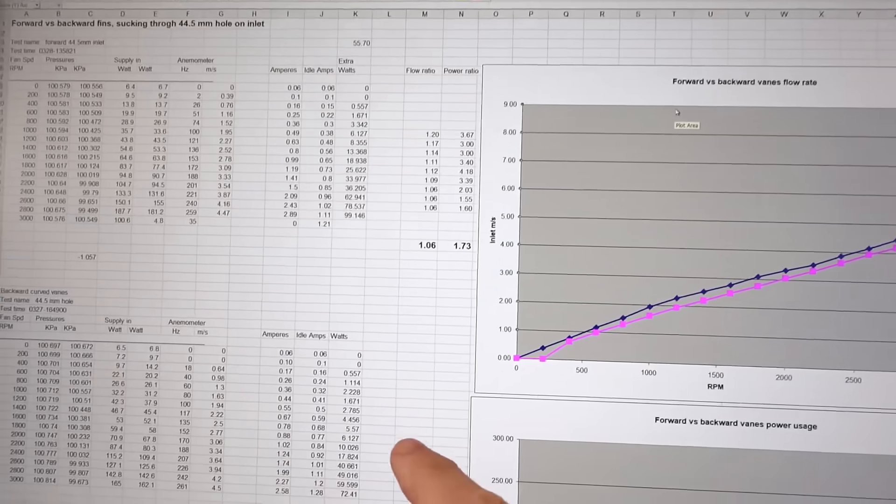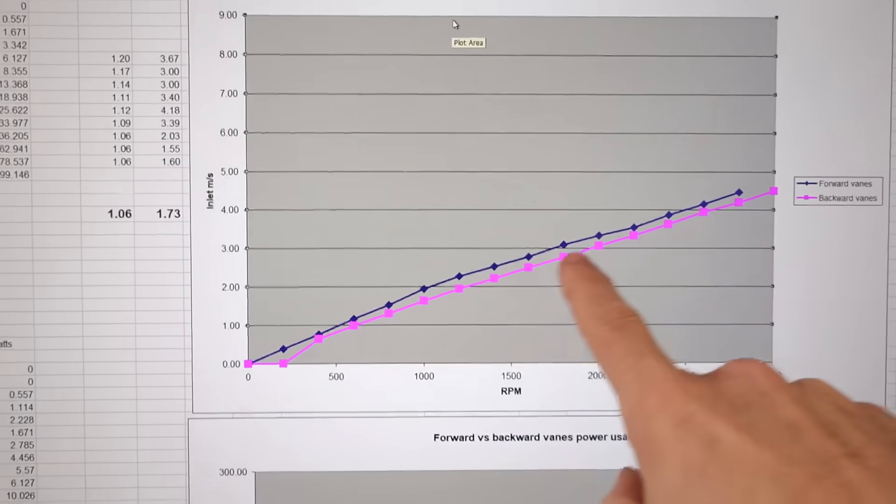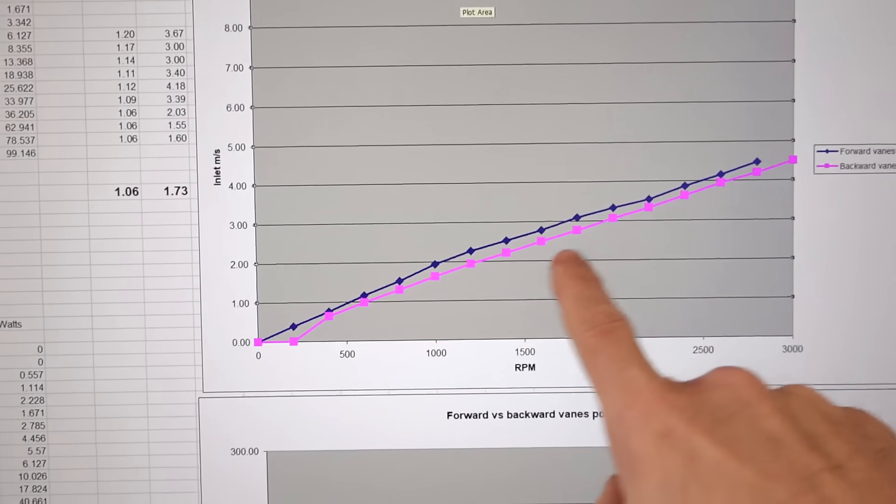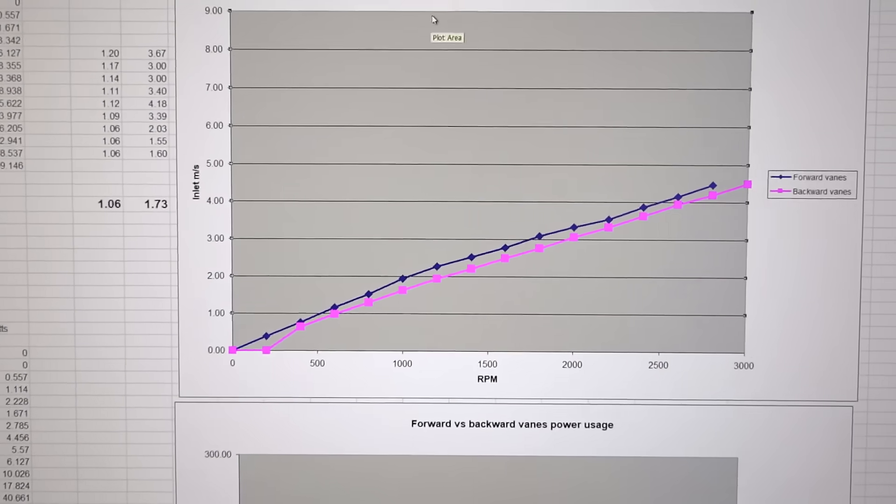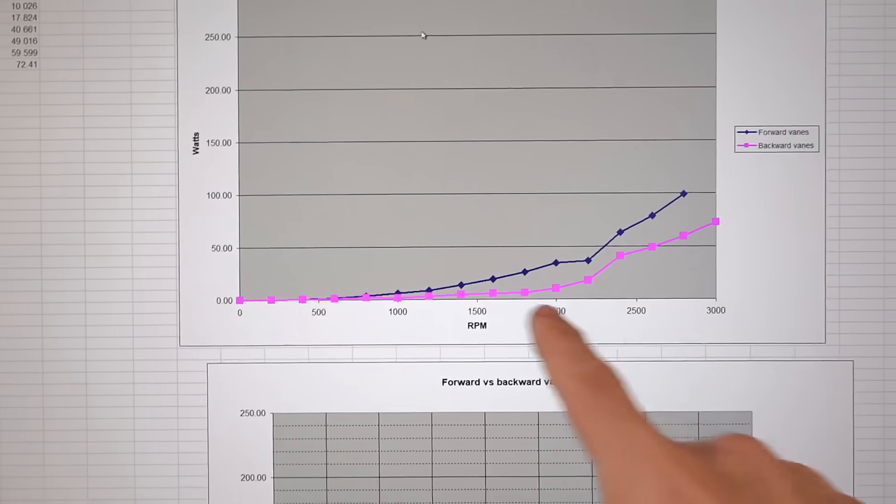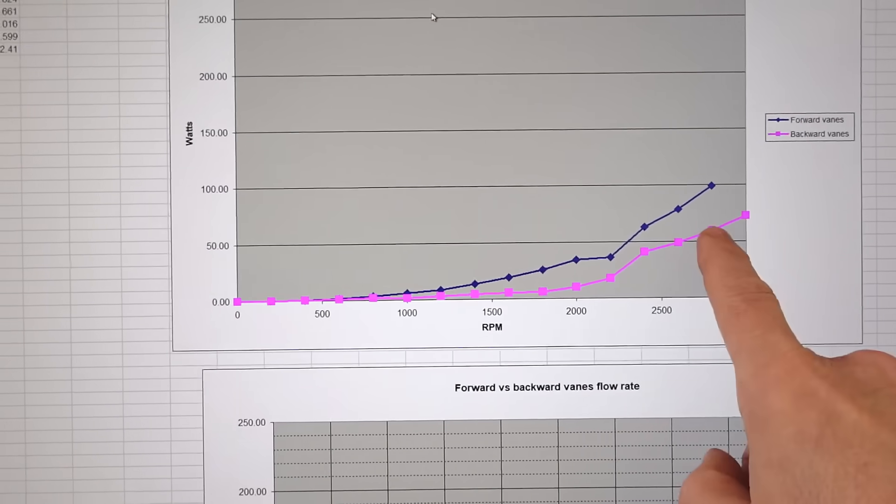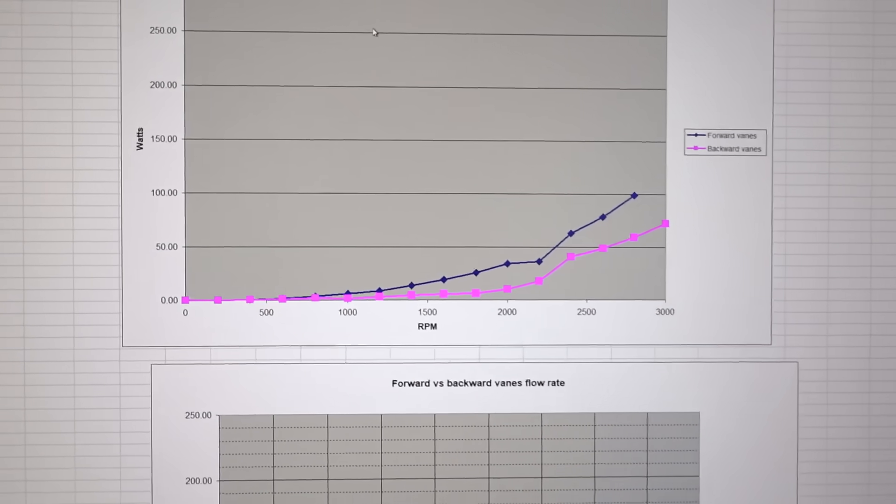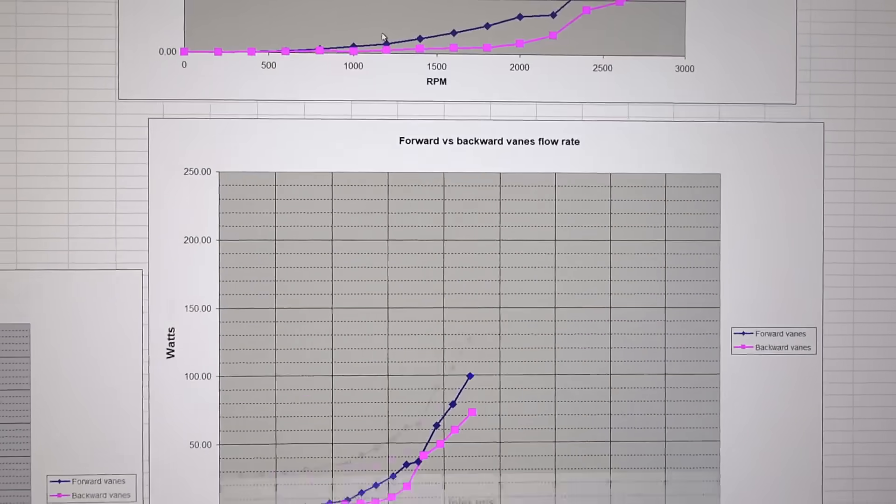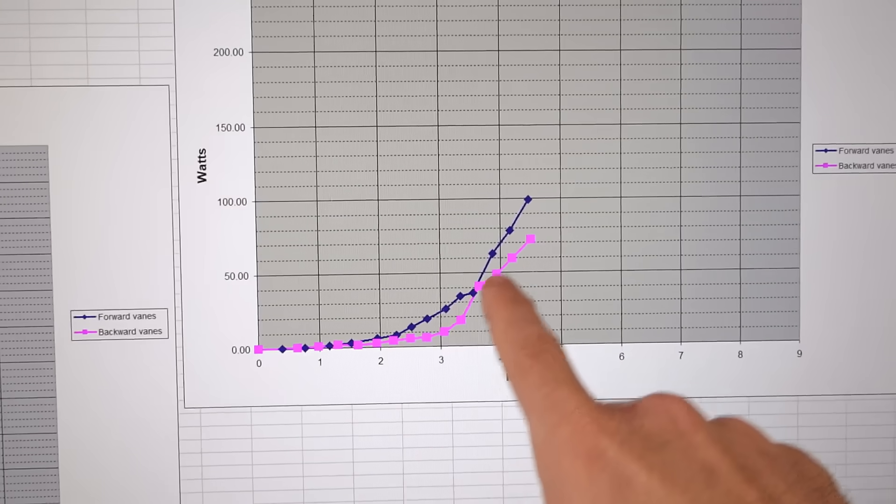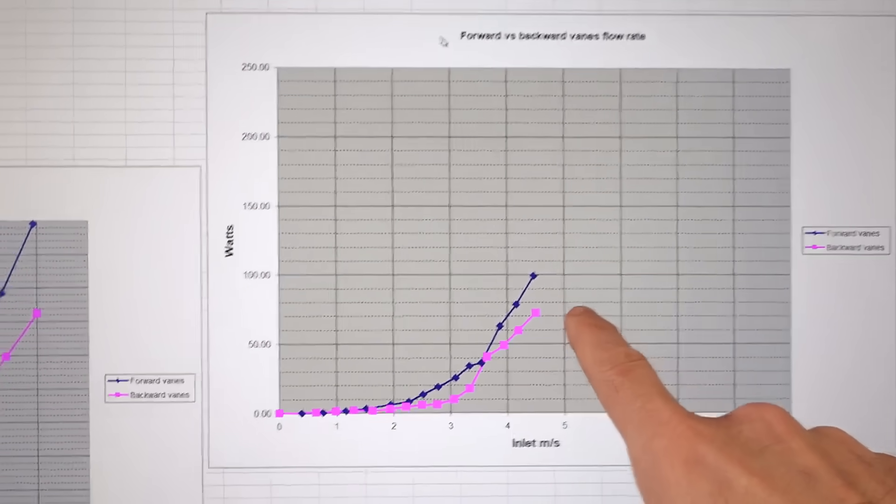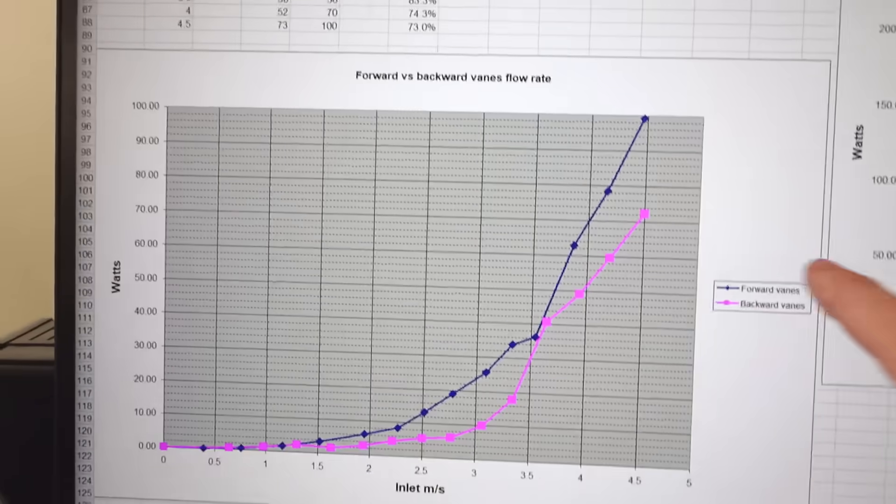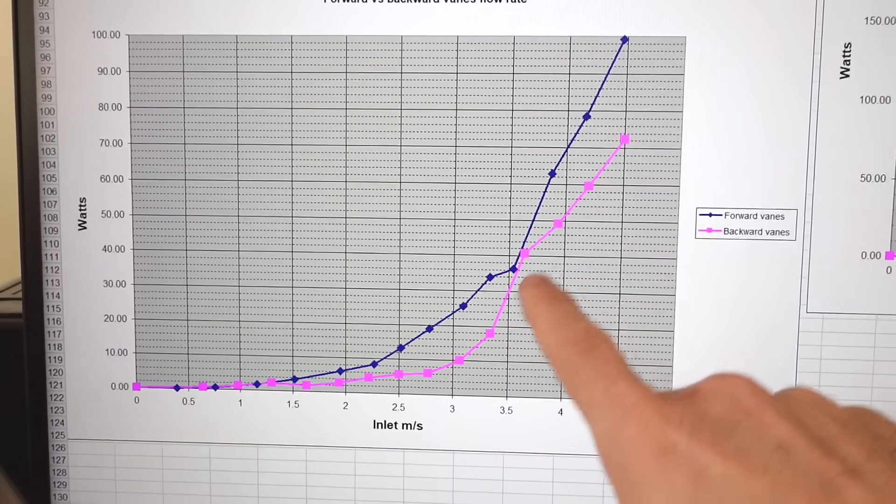I also ran that for the backward facing ones, and the flow rate is of course much lower. The flow rate difference isn't very large, but if we look at the power usage, that difference is quite substantial. Plotting flow rate versus power usage, this is on the same scale as before. Zooming it up a bit, the difference is quite large.